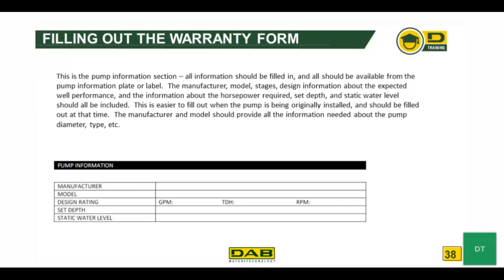This is the pump information section. All information shall be filled in and all should be available from the pump information plate or label. Manufacturer, model, stages, design information about the expected well performance, and the information about the horsepower required, set depth, and static water level shall all be included. This is easier to fill out when the pump is being originally installed and should be filled out at that time if at all possible. The manufacturer and model should provide all the information needed about the pump diameter, type, etc. This will give you more information about the specific pump installation that can be used to determine the state of the well and the warranty itself.